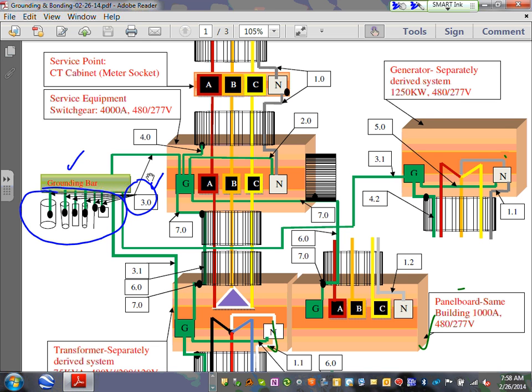So all these guys, from the water into the beams, into wire, into a plate, the NEC code book defines a copper plate with certain dimensions. You bury it in the ground, and that will act as your connection to the ground. Can I get you to understand this is the grounding bar? The code requires you to tie to only one thing, Adam, water or concrete if you have it. But if you have other things in the building, you have to tie to them. So if your building is concrete, you end up tying to the foundations of that concrete. If it's steel, you end up tying to the steel. And you end up also tying to the water.